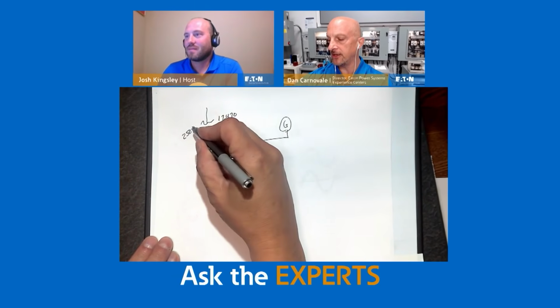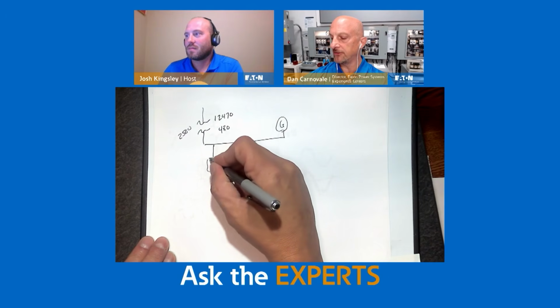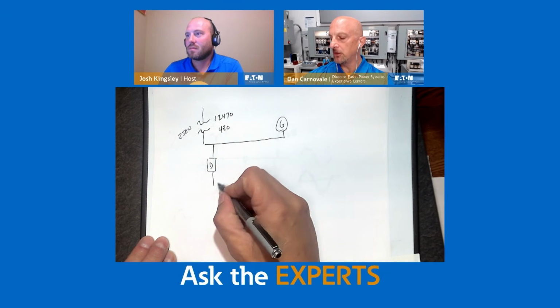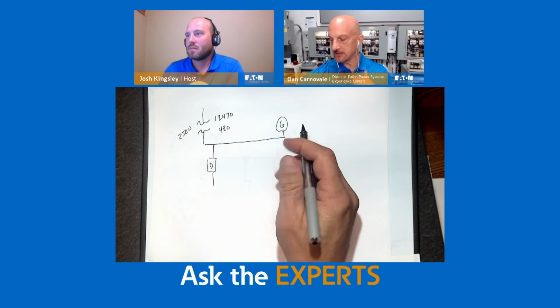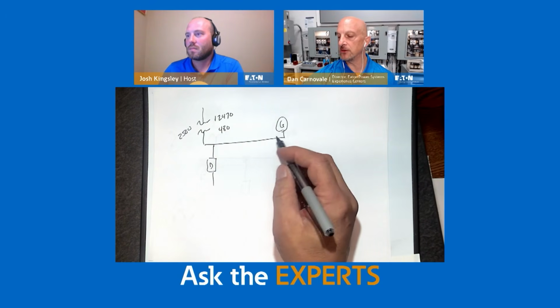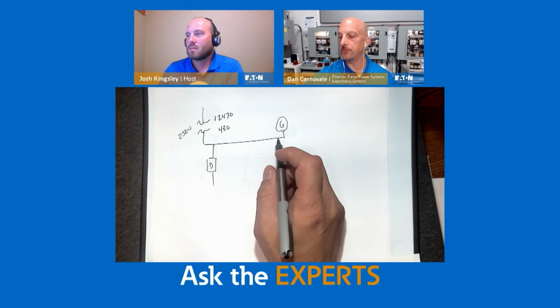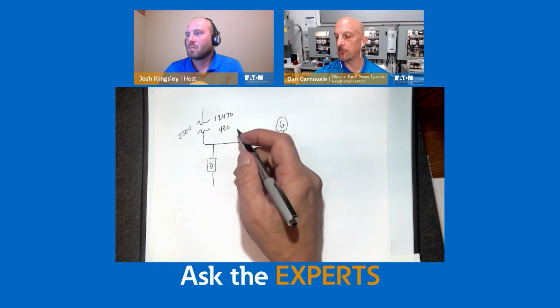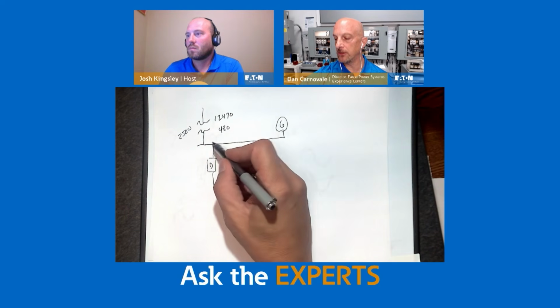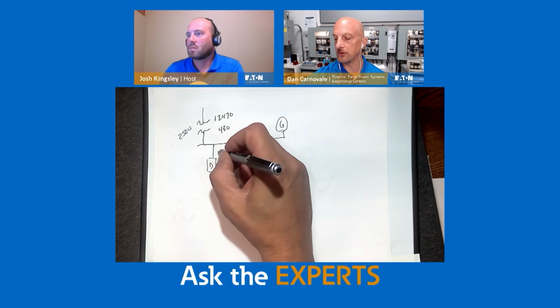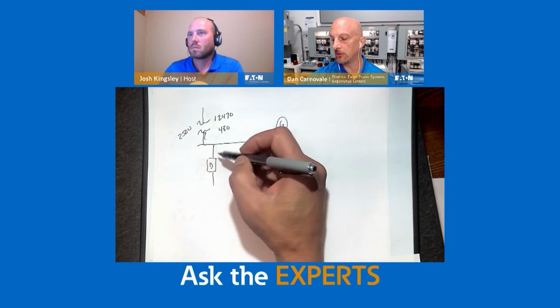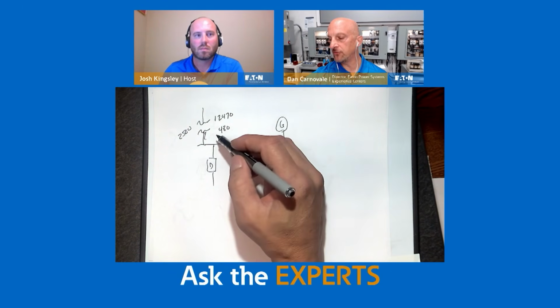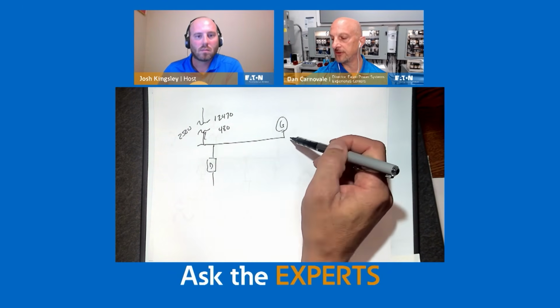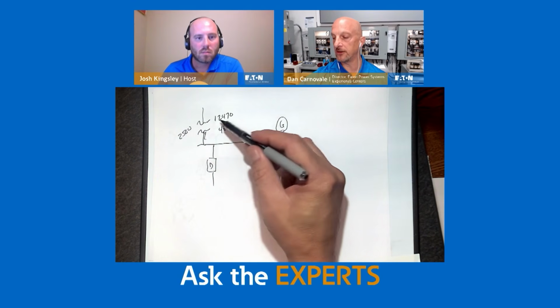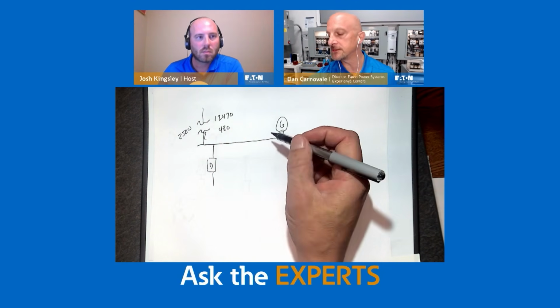I think so. So 12.47, 2500 kVA, lots of harmonics. Everything on here is on drives, so they're running everything, and he says the harmonics disappear when they go on generator. I don't know if he means specifically, and maybe you could have a follow-up question, but the current, again, has to flow somewhere. So the current's going to typically flow out and back on the transformer out to all the different drives. So if we transfer to the generator, we would have the same thing. If the generator is running in parallel, likely a lot of the harmonics will still go back to the utility, as that's a lower impedance in terms of current.